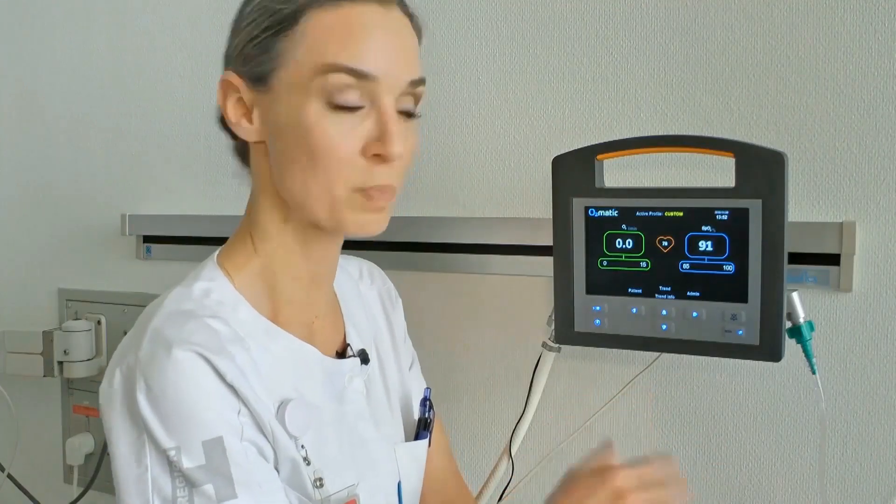In O2matic, any saturation range between 85 and 100 percent can be set. Also, the oxygen flow can be set between 0 and 15 liters per minute. If the saturation falls below the target range or if the pulse rate is outside normal, an alarm sounds.